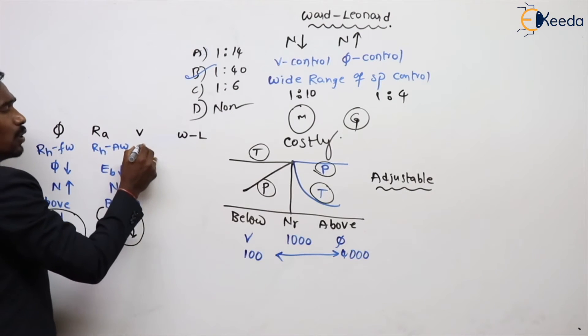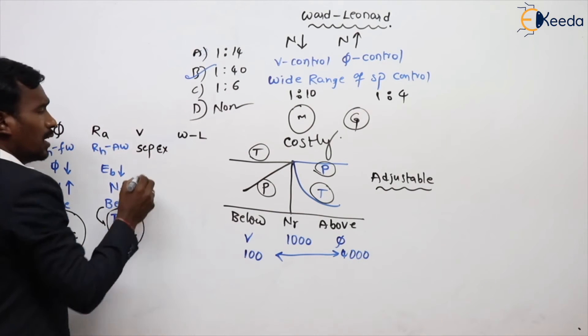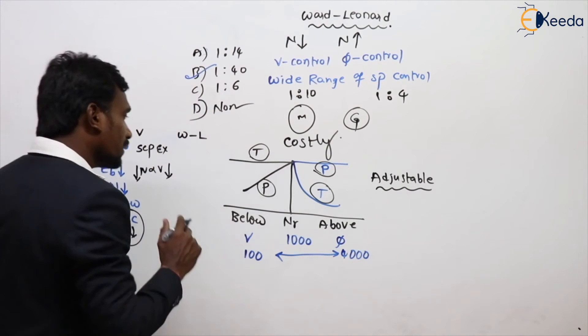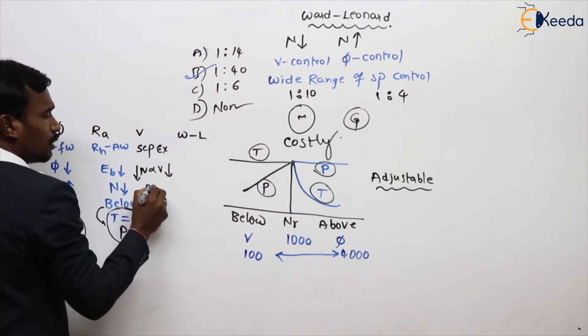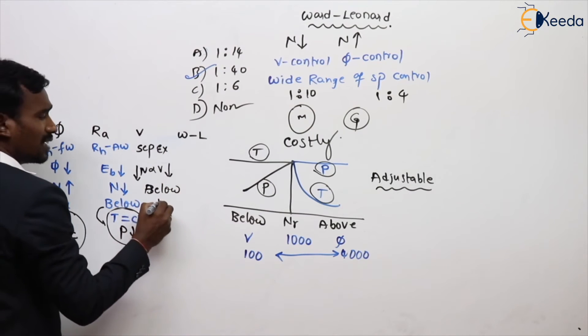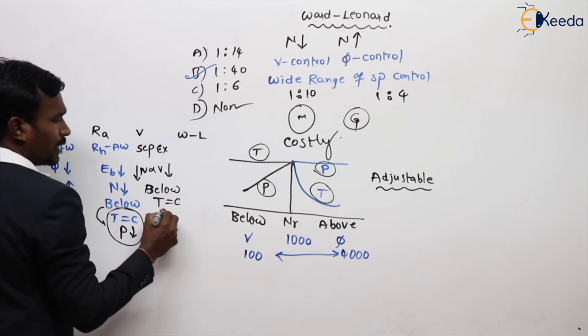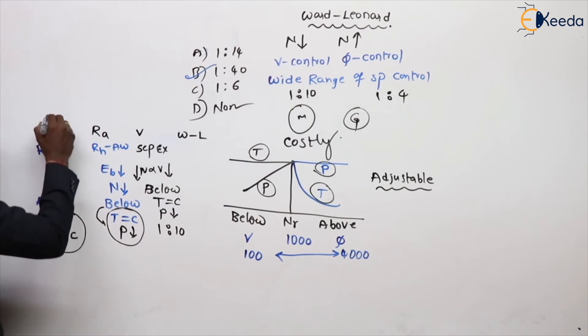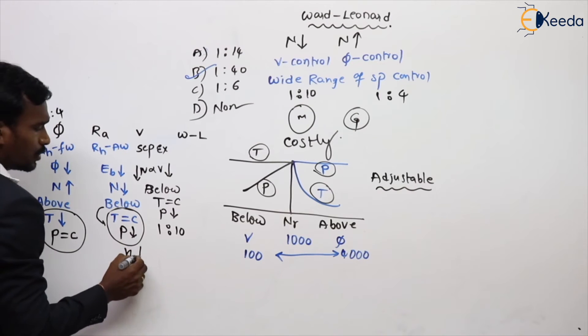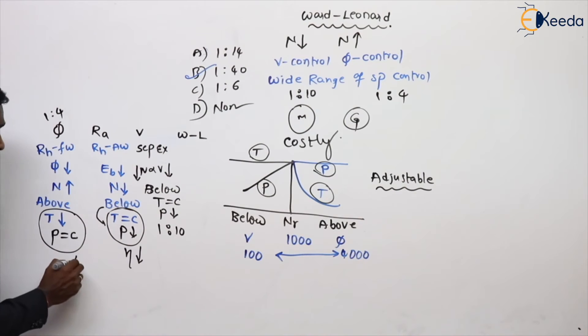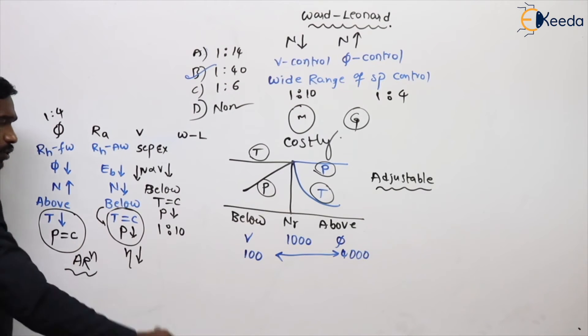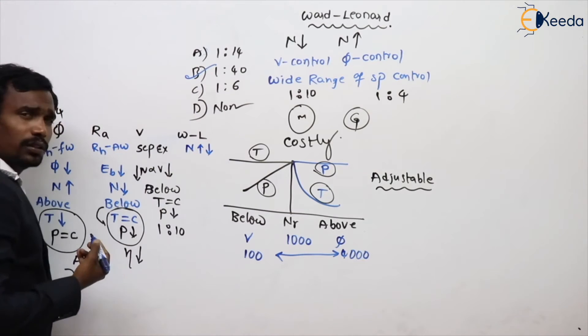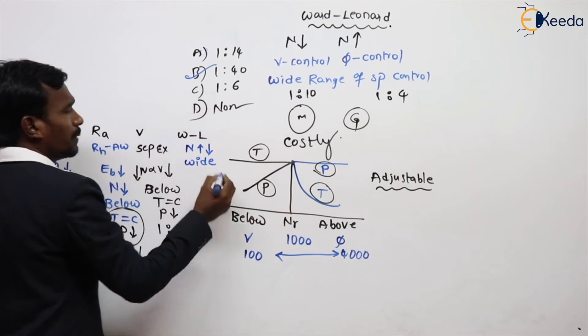For voltage control, this is only applicable for separately excited motors. The speed is directly proportional to voltage, so by controlling the voltage we can control the speed. Be careful — don't increase the voltage to increase the speed. This is also a below rated speed method — constant torque variable power drive — with a speed control range of 1:10. For flux control, the range is 1:4. Ward-Leonard covers both above and below rated speed, giving a wide range of speed control with a 1:40 range, but it is comparatively a costly method.